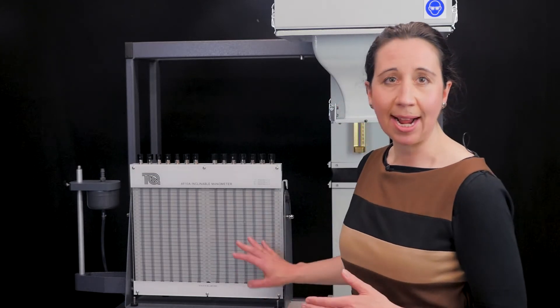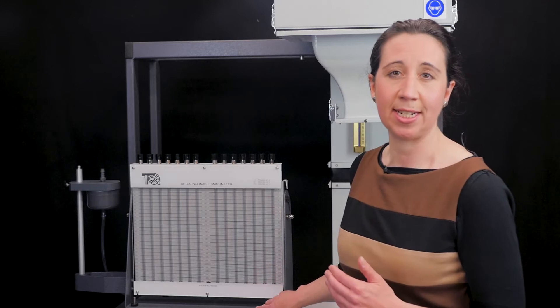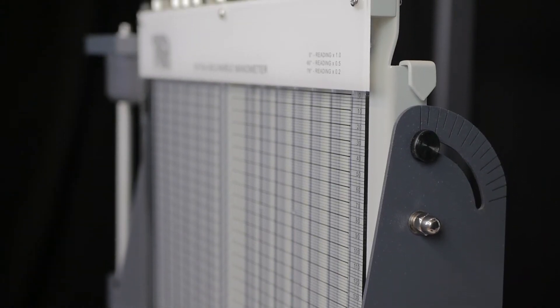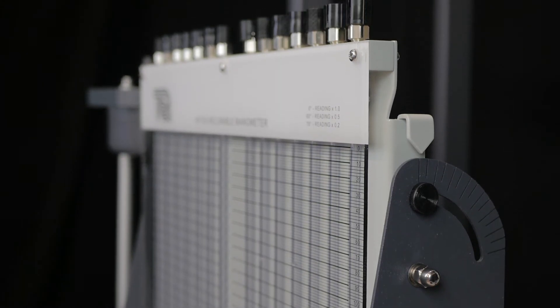It also has an adjustable angle using the thumb screw fixings allowing you to move it from fully vertical to 80 degrees. These markings on the side show angles in 5 and 10 degree intervals. This increases the sensitivity of the manometer allowing you to see small pressure changes more clearly.